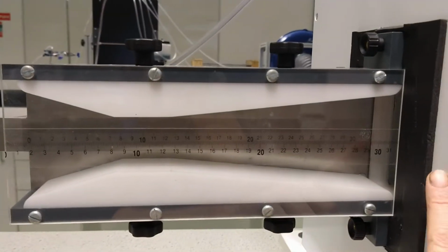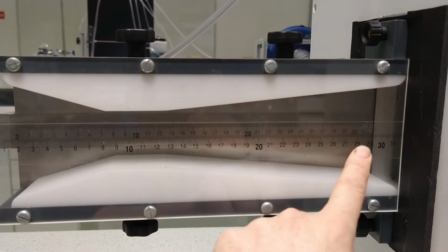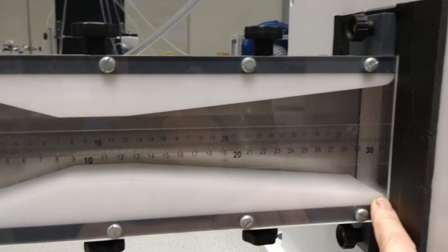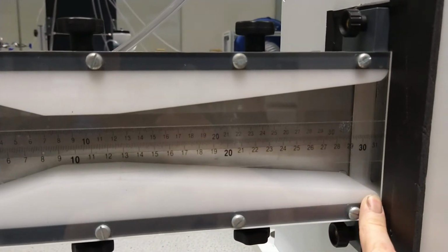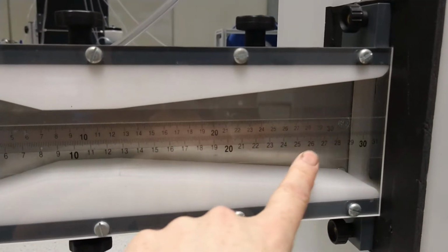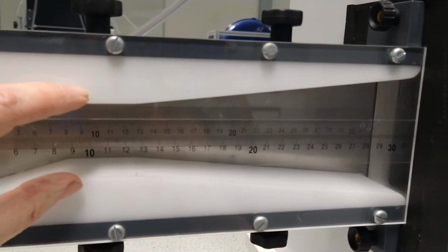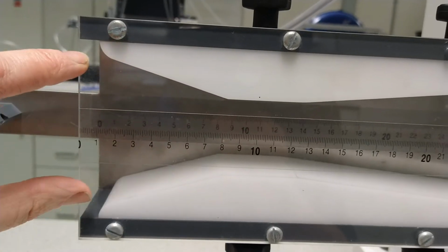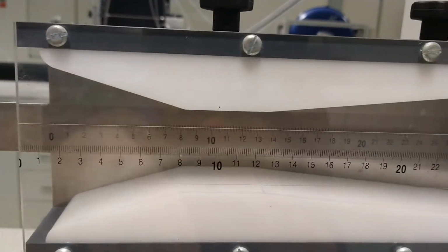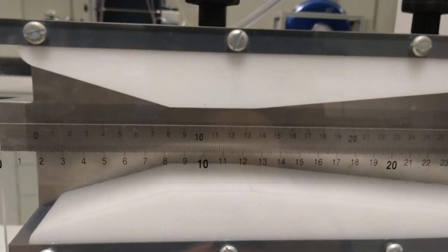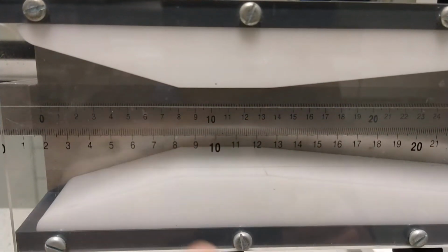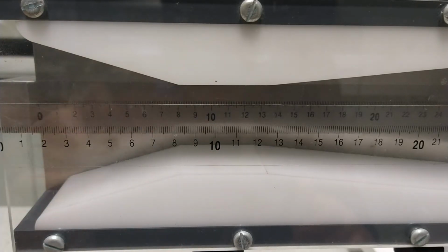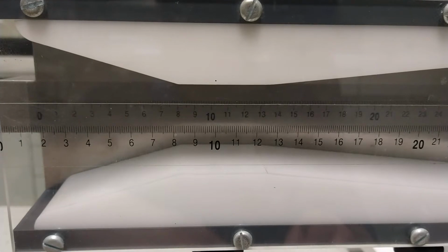In this case, you have the air coming from the chamber in this direction here. It comes out at a particular cross-sectional area out here. So you have a wide height here, and it gets narrower as it goes along, and you have the narrowest section of the Venturi here. The throat of the Venturi is here. Then it widens out again as it exits out to atmosphere. I believe this is what they call in the manual the liners reverse configuration, where the throat section is about 100 millimeters from the exit over here out to atmosphere.